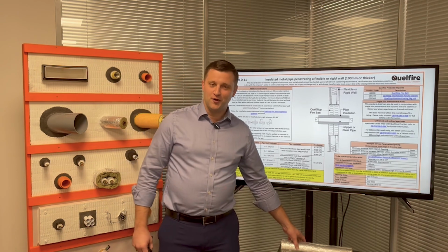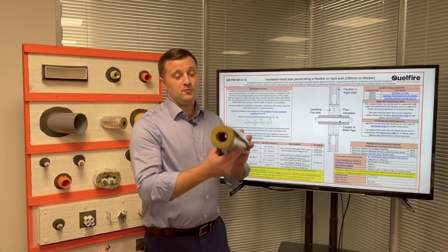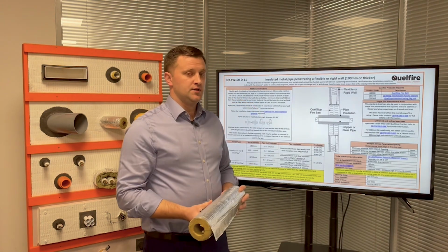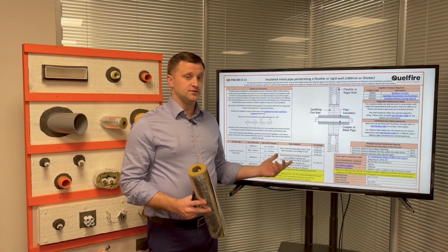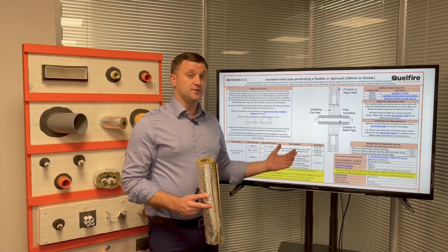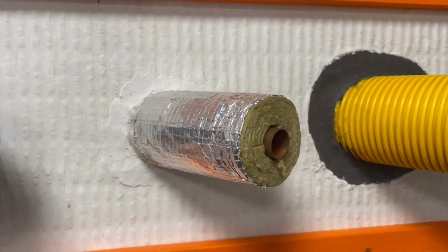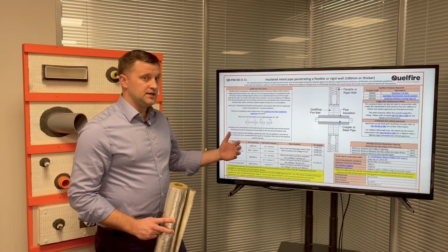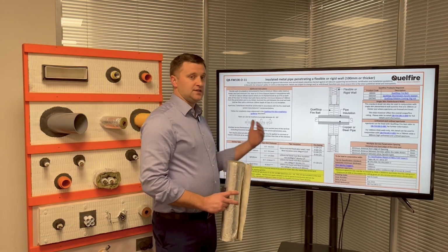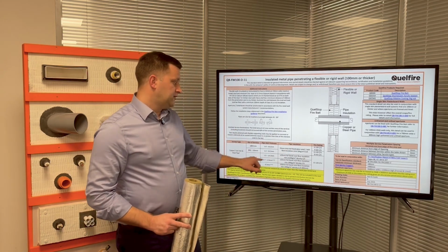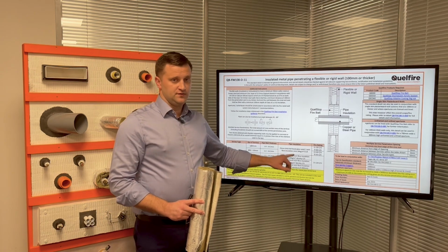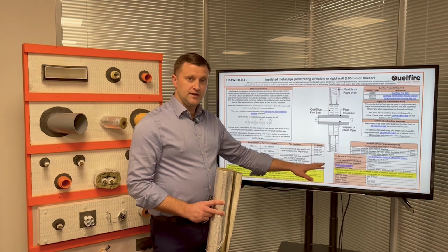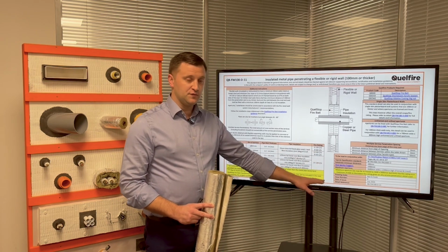So first of all, what is rock fibre insulation? Well, it's this material here, so it's intended for insulating the pipe, but in the context of some of the fire stopping details, it is used to help slow down the spread of heat, if you like, through the fire seal as well. So it's important to identify the most appropriate standard installation detail and pay attention to the different types of insulation that are referenced on there, because different insulations, different thicknesses will ultimately give different fire ratings.